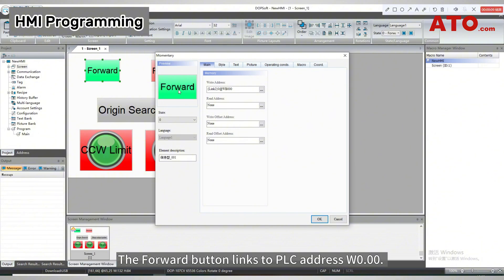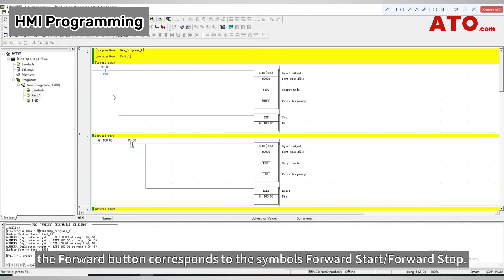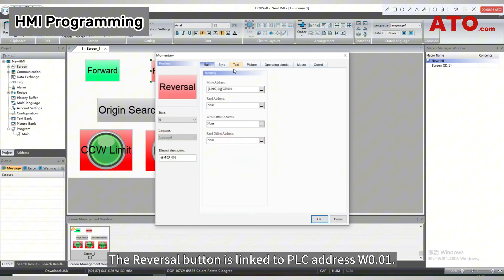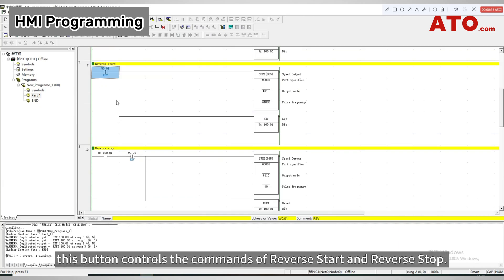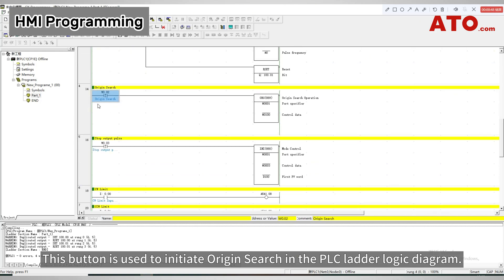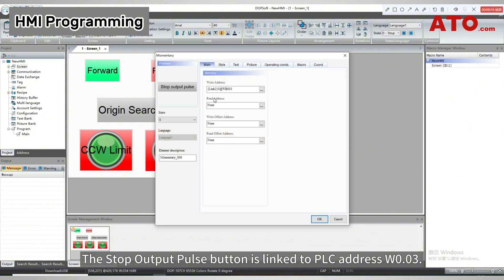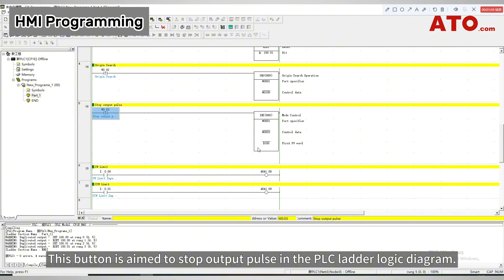The forward button links to PLC address W0.00. In the PLC ladder logic diagram, the forward button corresponds to the symbols forward start and forward stop. The reversal button is linked to PLC address W0.01, controlling the commands of reverse start and reverse stop. The origin search button is linked to PLC address W0.02, used to initiate origin search. The stop output pulse button is linked to PLC address W0.03, aimed to stop output pulse in the PLC ladder logic diagram.